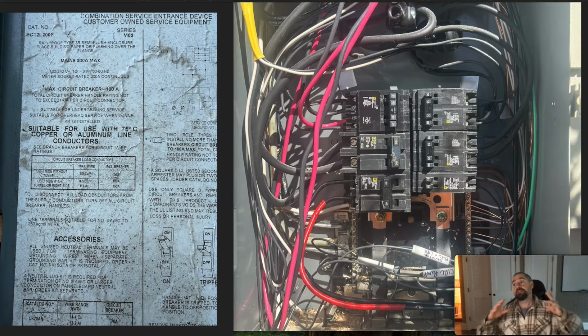In this case, this is a hot bus panel. Any backfed breaker connected to that bus bar is a supply side connection per the National Electric Code. It is on the supply side of all the other service disconnecting means. So, you know, say you had 5 double pole breakers in there, you slapped in a 6th double pole breaker, which is your PV backfed breaker.